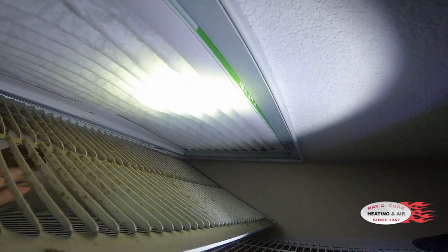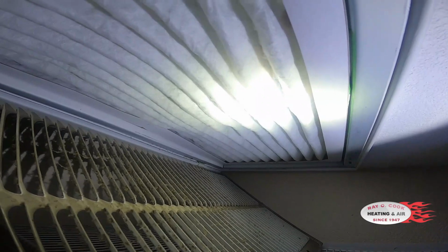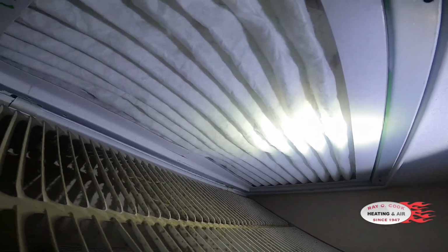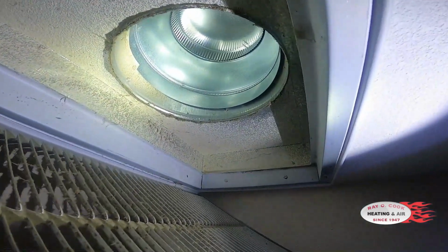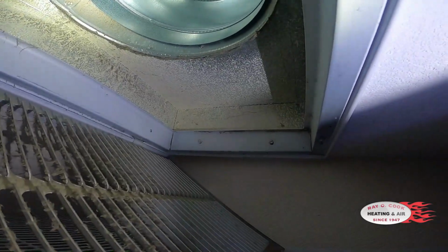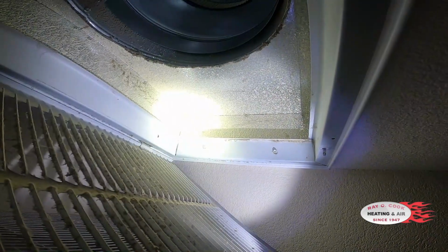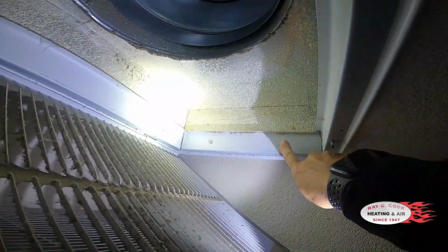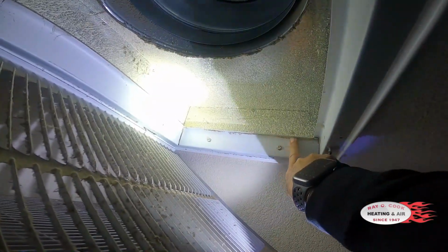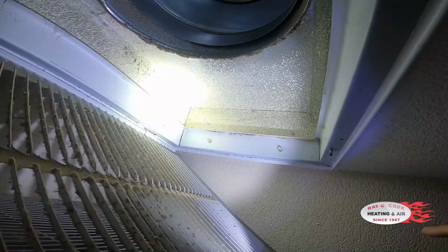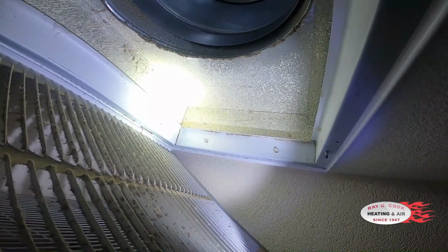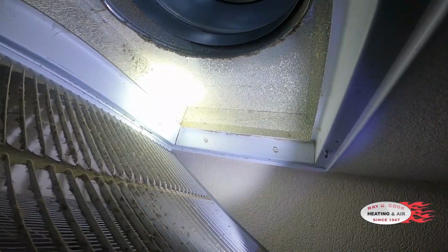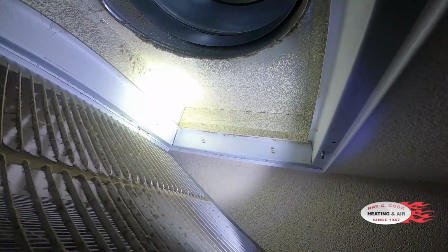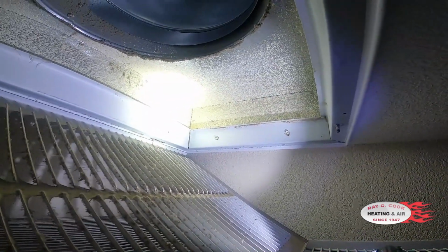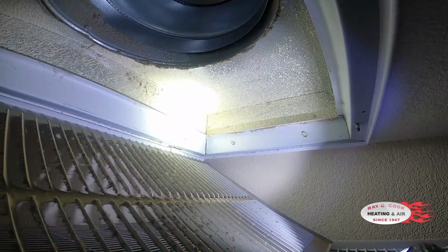So here's a regular filter grill. And when we open it up, we see the customer has changed the filter recently, brand new white filter. So when we pull this down, we can see the bypass that we've been talking about. So in the back corner there, you can see all of that dirt on the upper side of the filter. So what that means is that dust has gotten by the filter, and if it's there, it's everywhere else in the system. So we know that we have filter bypass on this grill, and it doesn't matter how efficient this filter is, we've got air going by it.